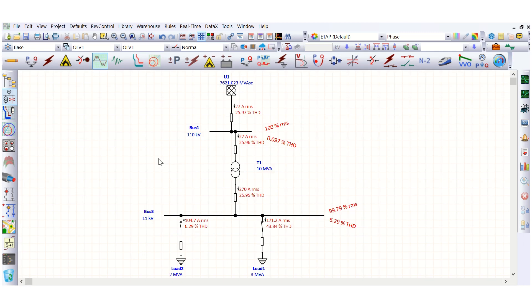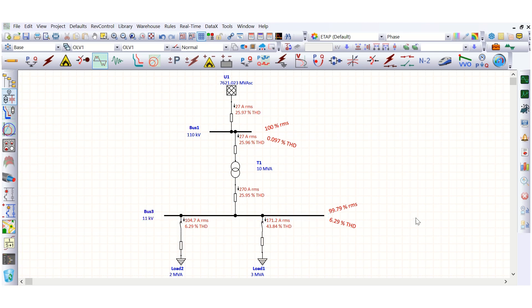Now I will go to Part 2. In this video, using the IEEE 519 standard tables, I will validate whether the total harmonic distortion values — voltage distortion and individual current distortion — obtained from the ETAP simulation software are acceptable or not, or whether mitigation using a harmonic filter is required.